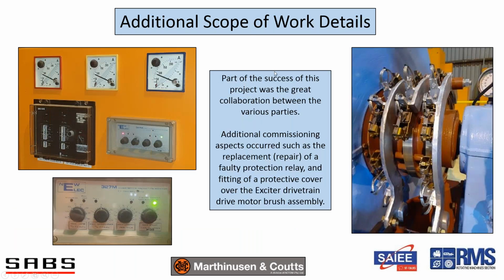Other additional scope of work, and I must mention this, Seth will comment about this as well. You know, there's always some awkward moments in these things where you want to hand over your part of the project, but then a protection relay starts giving hassles, and I think it's fair to say there was very good collaboration between all the parties. One of these protection relays prevented us from starting a motor. We had to get a new one. We also, this is the exciter drivetrain slip ring brush gear and slip ring assembly. It has never had a guard over it. So what we did is we made a guard as part of the project while we were busy.